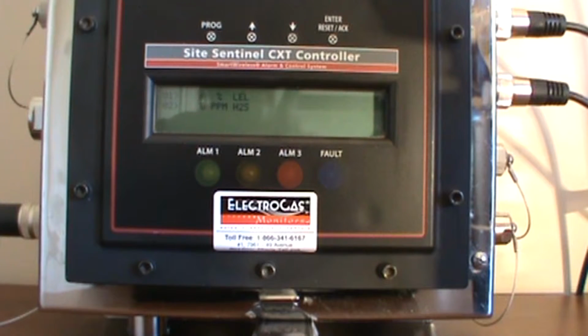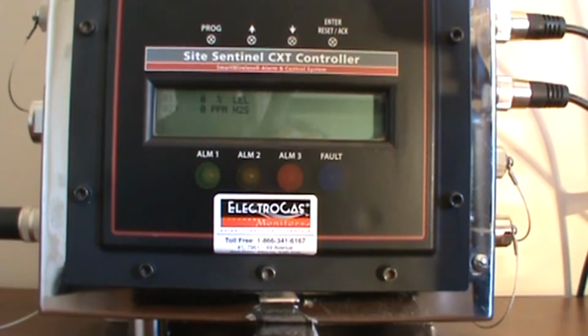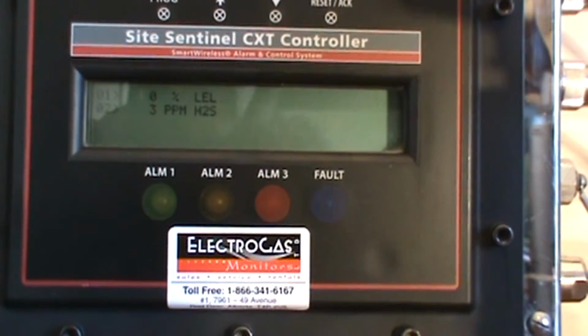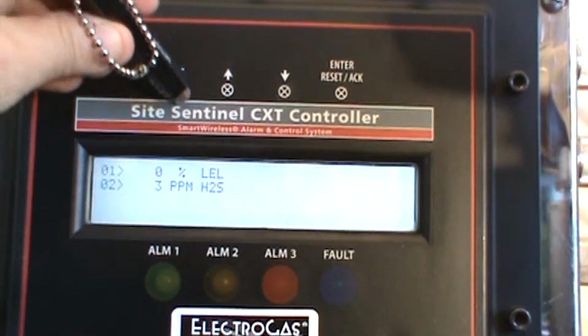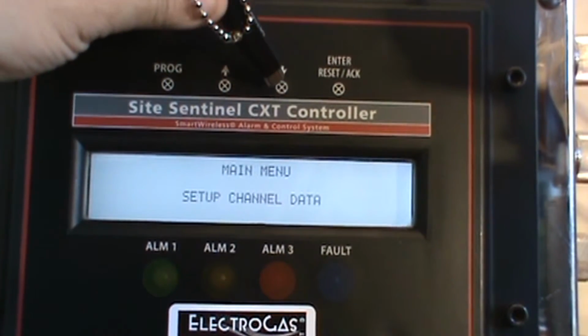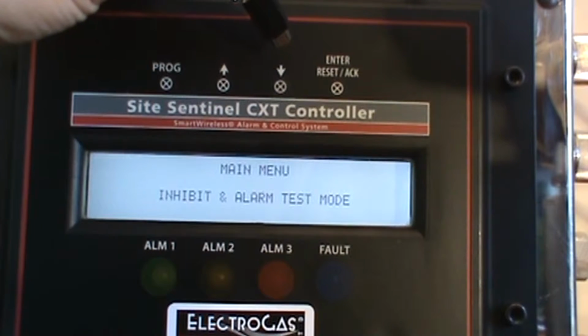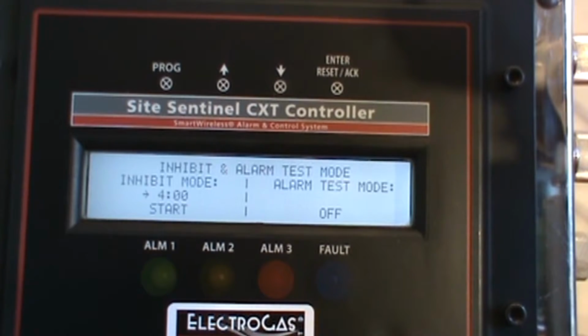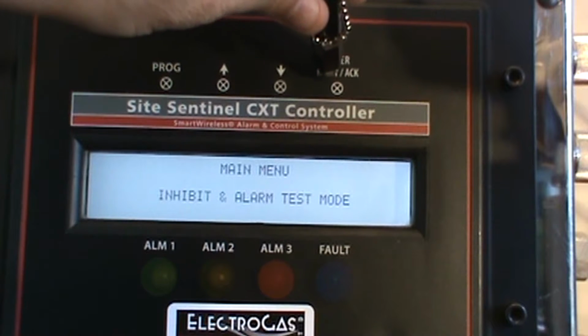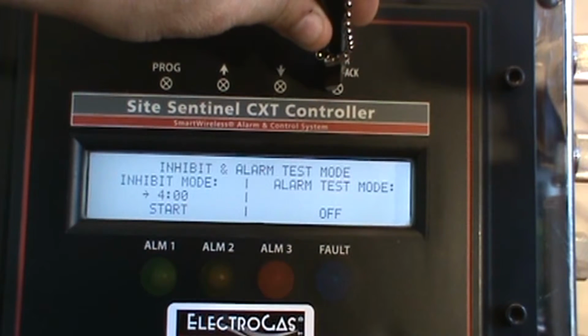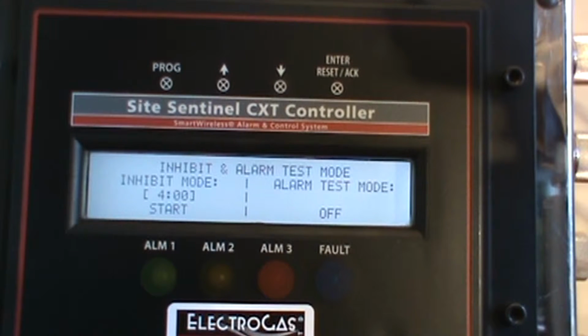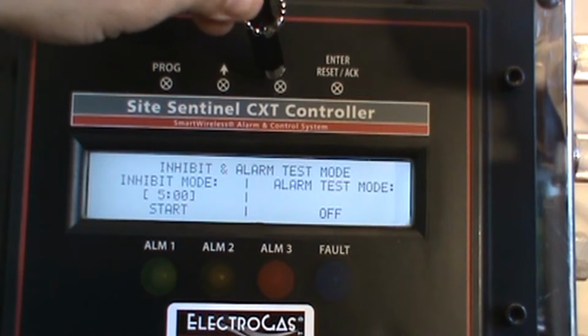To do that, you will enter into the program mode. And using the down arrow, inhibit and alarm test mode, press enter, and we will now notice on the left hand side of the screen we're in inhibit mode with the arrow next to the 4. The factory default is a 1. If you wish to change that, you would simply press enter by the 4 in this case, and using your up and down arrow change it.